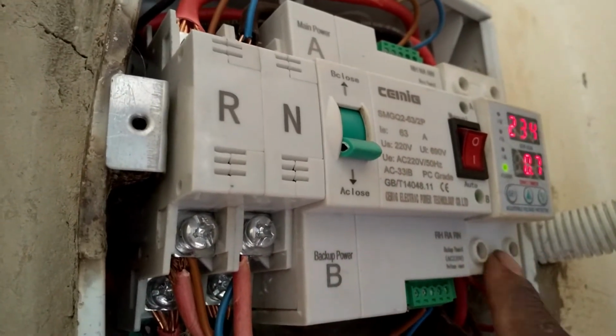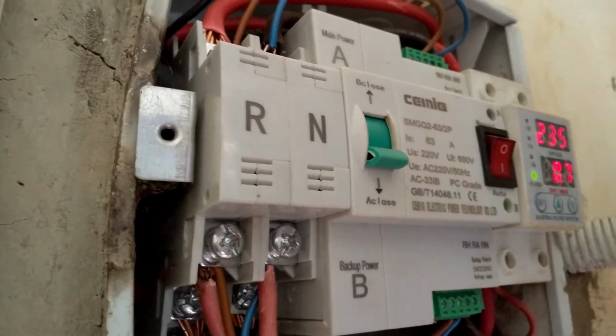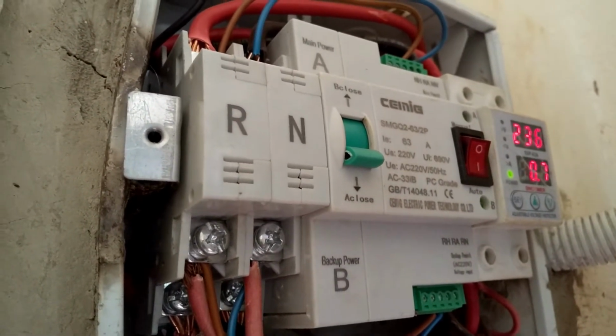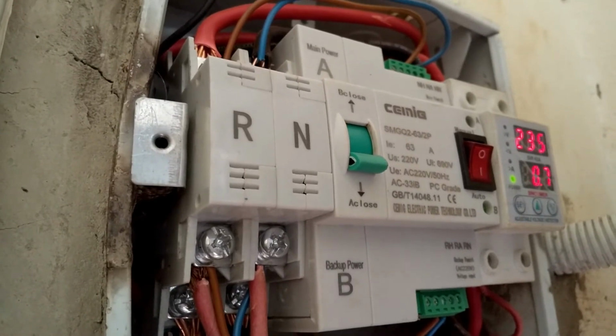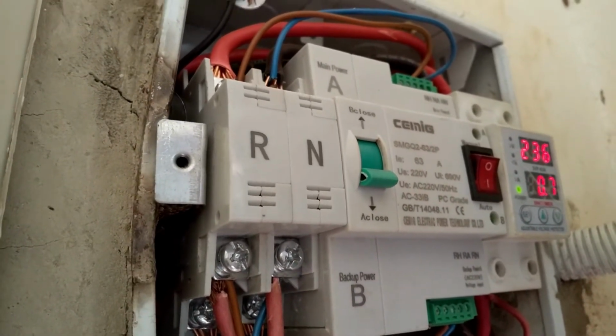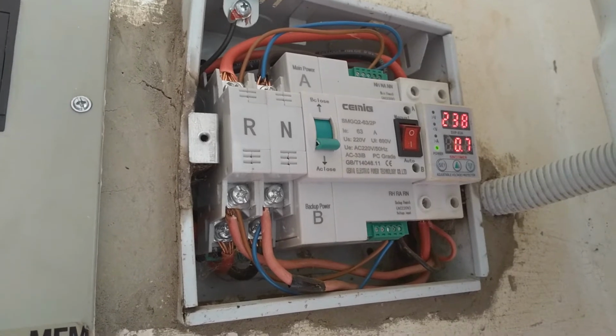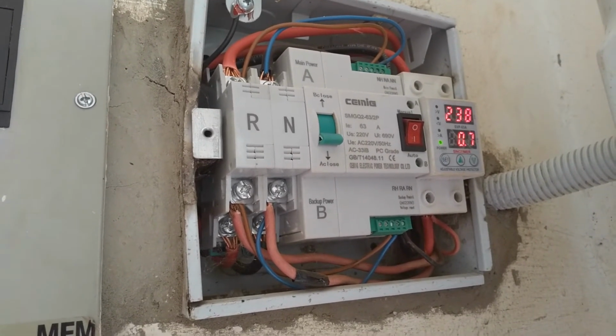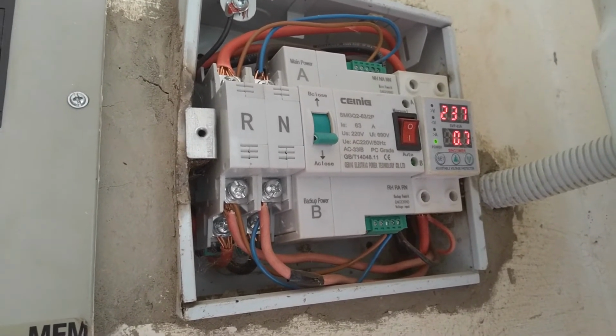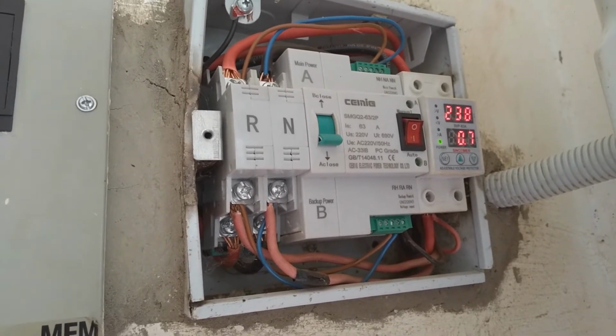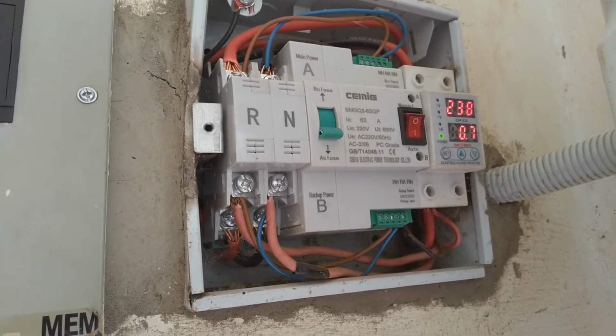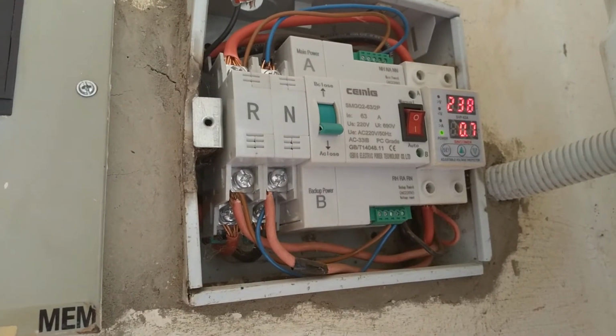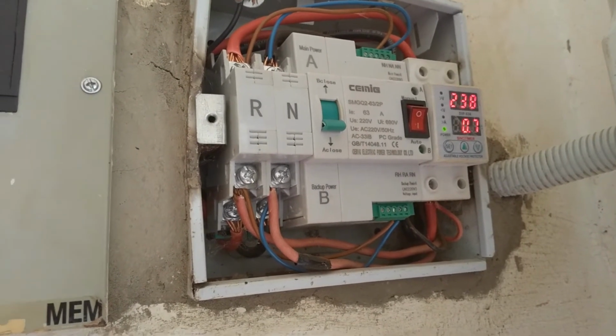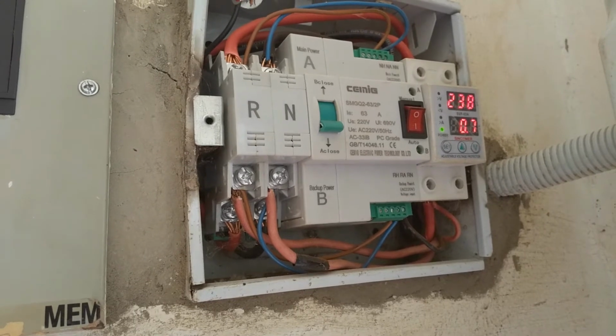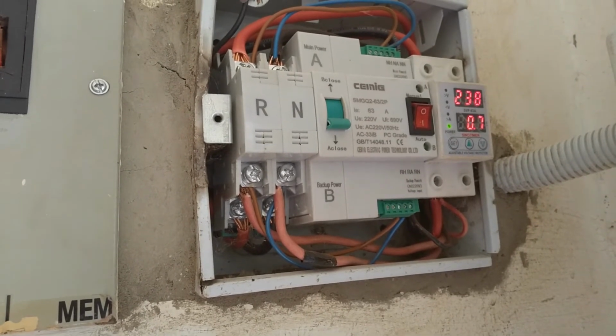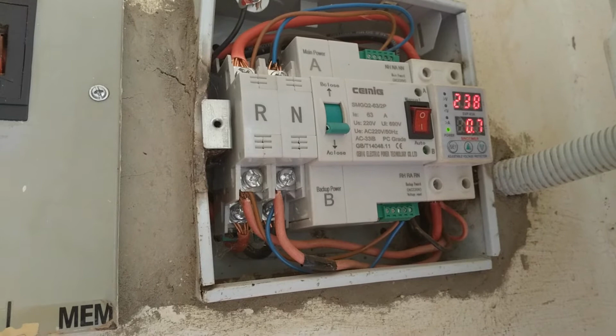So mine is rated 63 amps, and it does the job of protecting my installation against such problems. In this build I've incorporated an ATS. This is an automatic transfer switch, because here we have two sources of supply, the grid and my simple power wall. So in order to transfer power between these two points of feed, you need something that will do the transfer for you. So that's where this automatic transfer switch comes in.